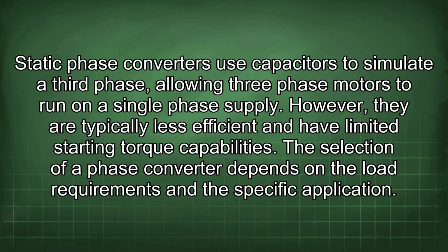Static phase converters use capacitors to simulate a third phase, allowing three-phase motors to run on a single-phase supply. However, they are typically less efficient and have limited starting torque capabilities. The selection of a phase converter depends on the load requirements and the specific application.